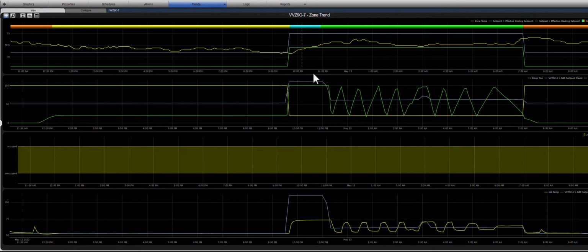So it took an hour to get to set point, basically because it went into minimum reheat and not maximum reheat. Maximum coil gives a very high discharge air temperature, but I'm not sure we have that mapped. Yeah, we do, right here, discharge air. So it was probably limited a little bit by discharge air temperatures, not that high, to get it to that set point. So to me, that's a little sluggish.